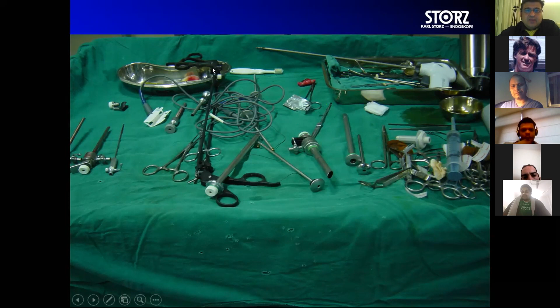Now this is a forceps. You see here it has a tip, the jaws, and what one should do is periodic cleaning. You can use a tray, like a Cidex tray, with water of at least drinking quality, and then you put in a decalcifying agent. Some companies, like Johnson, etc., make these. You open the instrument to whatever capacity you can, by removing the inner tube of the working forceps, the outer shaft, the handle, and you dismantle whatever you can. You put it in this lukewarm water at about 40 to 45 degrees for 30 to 45 minutes. So all the blood and debris in the nooks and corners is going to disintegrate, and finally you remove it from there. Then you go to the washroom and clean it.